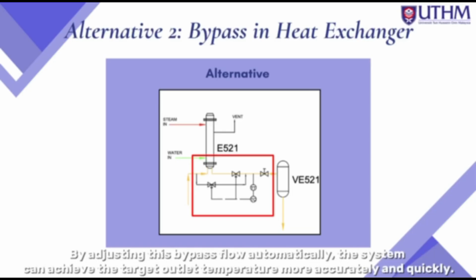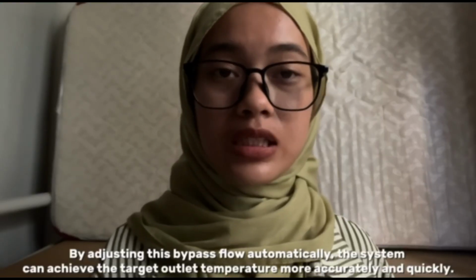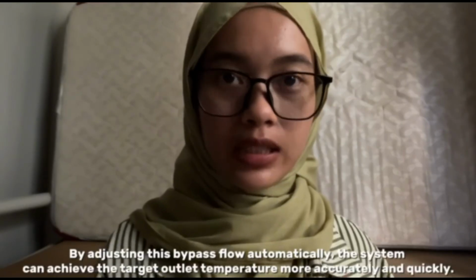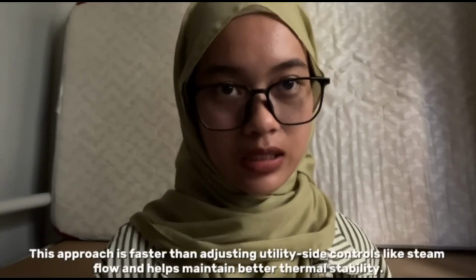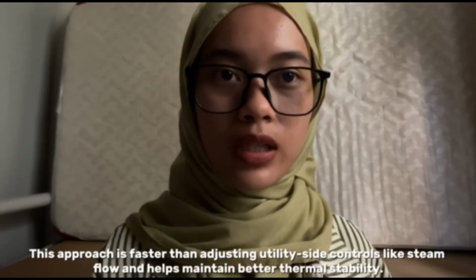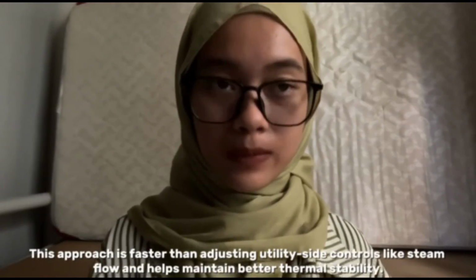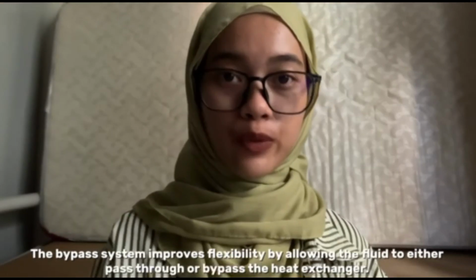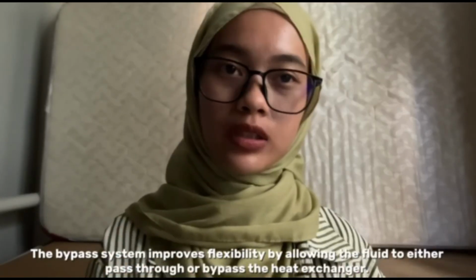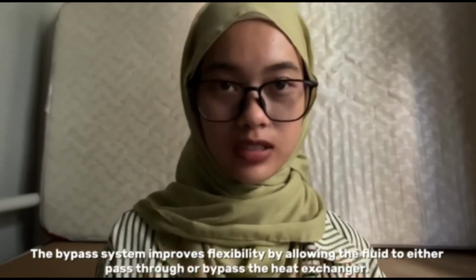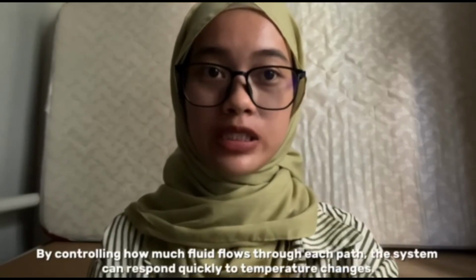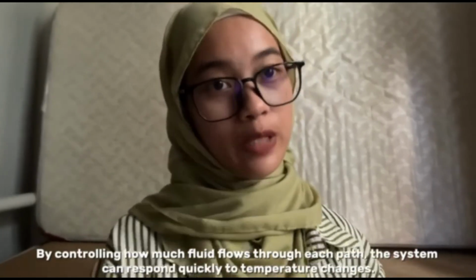By adjusting this bypass flow automatically, the system can achieve the target outlet temperature more accurately and quickly. This approach is faster than adjusting utility-side controls like steam flow and helps maintain better thermal stability. The bypass system improves flexibility by allowing the fluid to either pass through or bypass the heat exchanger. By controlling how much fluid flows through each path, the system can respond quickly to temperature changes.